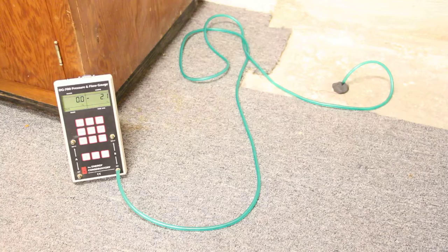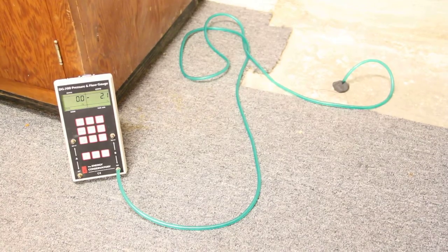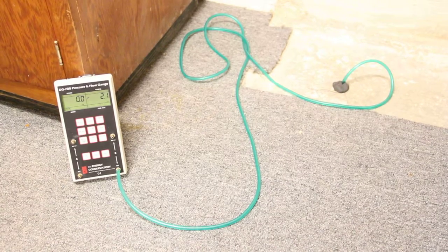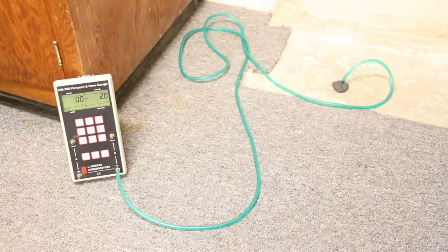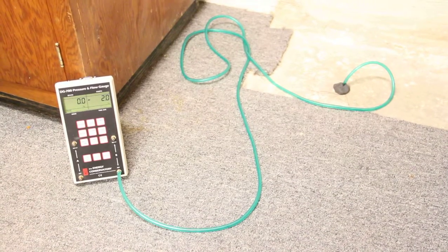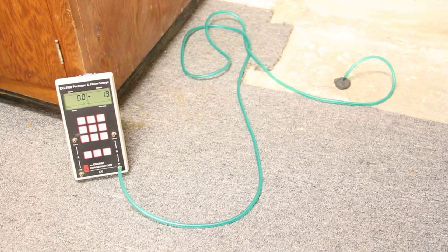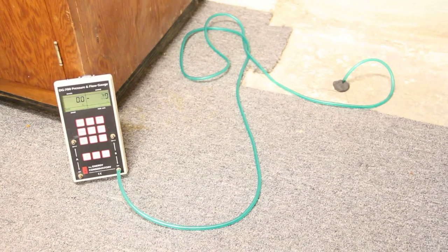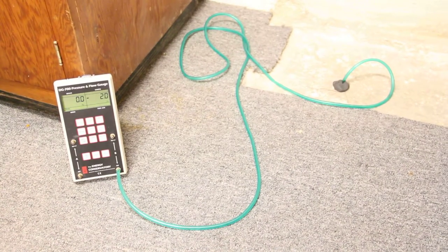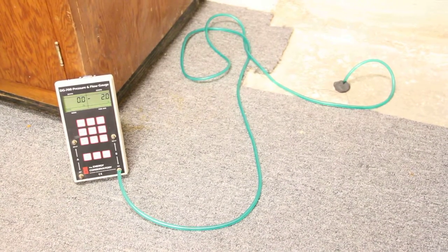And so we can see that there's a clear connection, changes the reading by about two pascals, and we're satisfied with that. That's a good connection between the suction point and this test point.